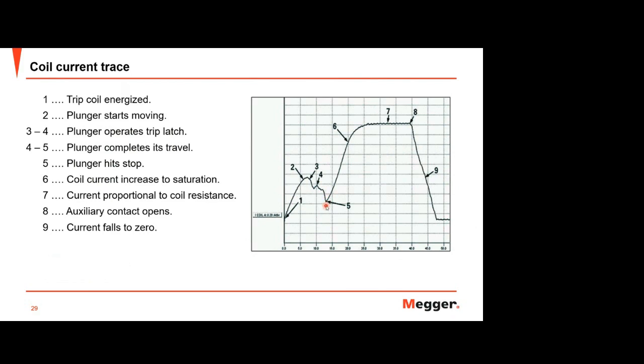Here you can see the magnitude of the current depends on the DC resistance of the coil. So if you see, the RDC of the coil will be in this area. So it will be constant after a short time. And then when the auxiliary contact 52A opens, the current will decay to 0. So this is the explanation of the coil current trace.